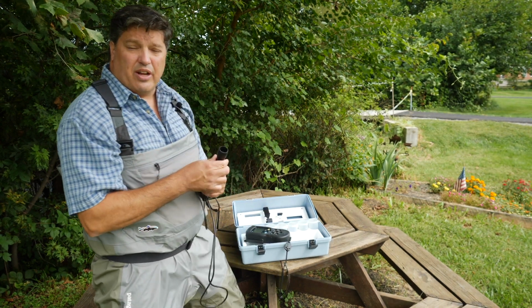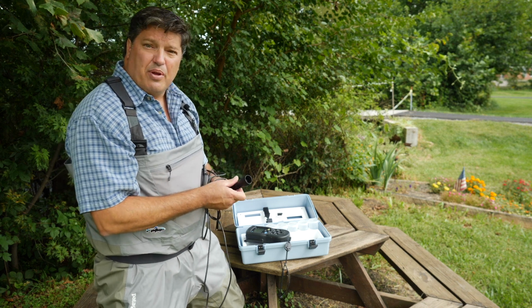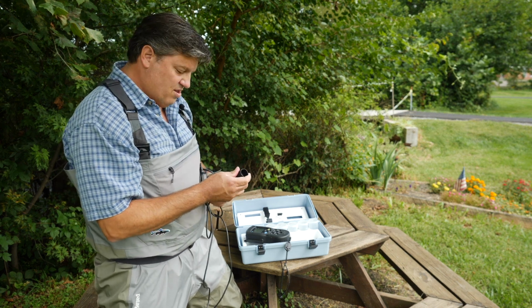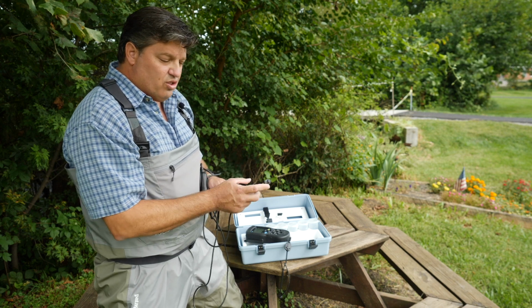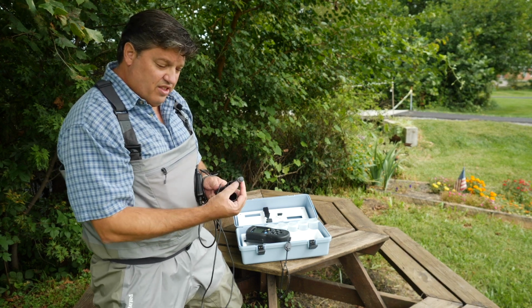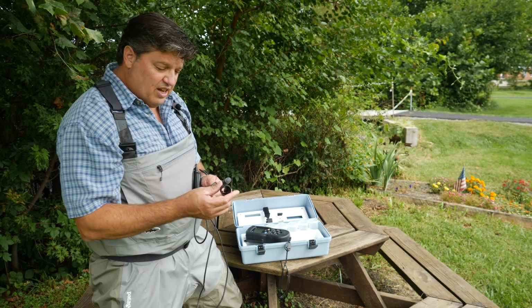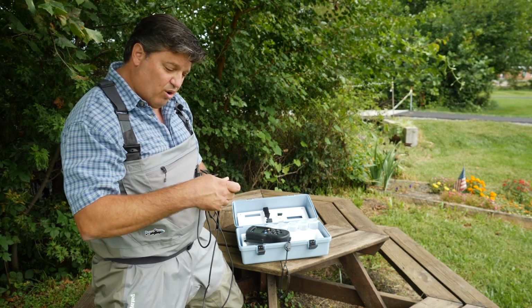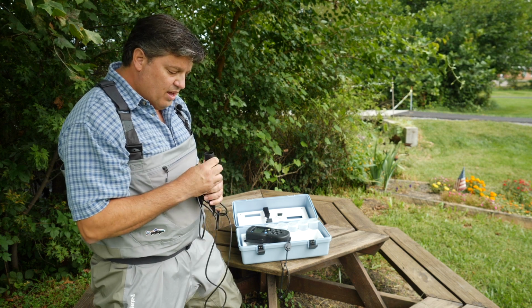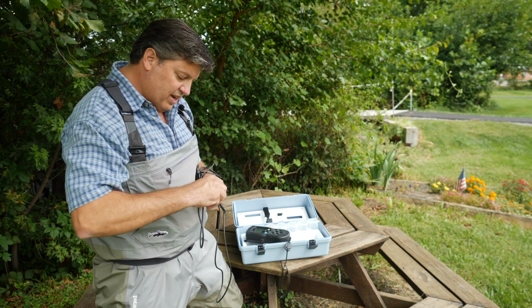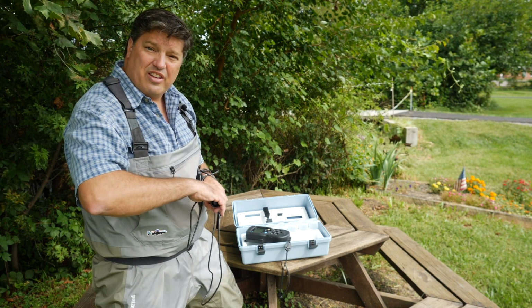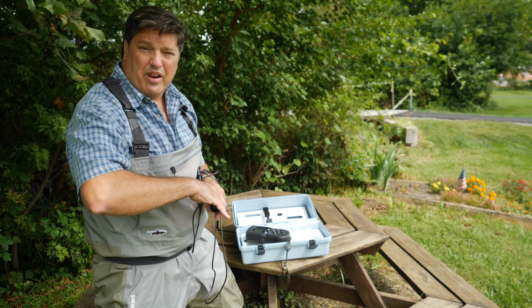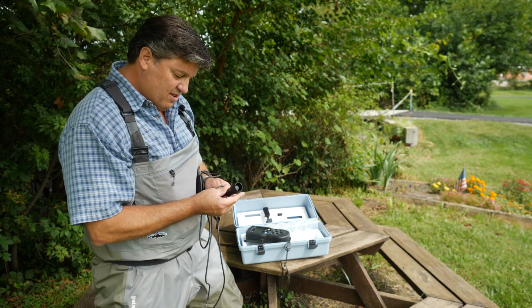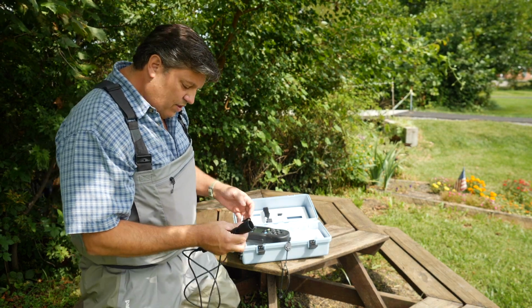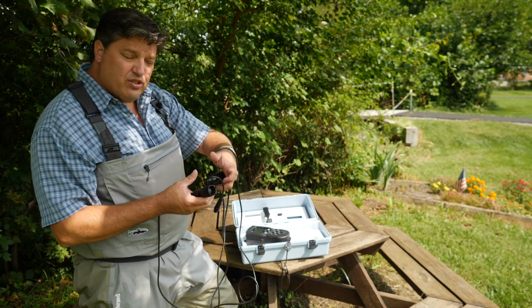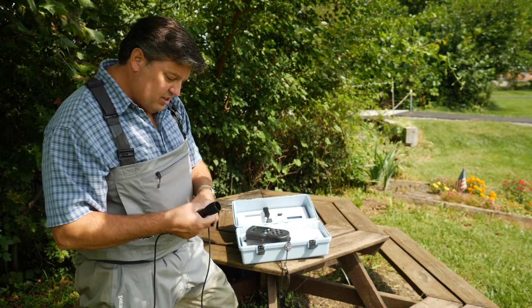The probe has a protective cover on it that can be removed. So this is the actual probe part, and the tip of the probe that senses the electrostatic current that goes through that. And this is just the protector that slides on to protect the very tip of that probe to keep it from hitting the bottom and getting dinged up. This probe is a couple meters in length and can be fully submersed.